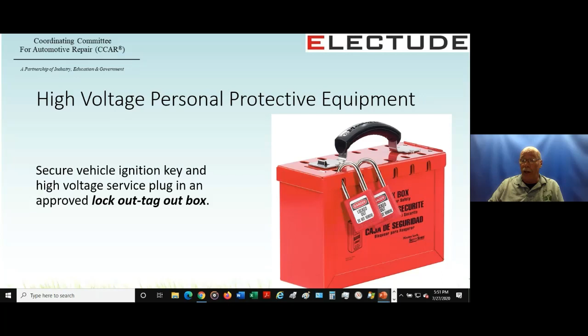As far as test equipment, minimum rating is IEC Cat 3 or better at 600 volts. That's the minimum rating that we are recommending. You want to check your test leads frequently. Have a teaching assistant or competent student leader check every voltmeter test lead that's going out in the shop during electric work, or for EV and HEV work.